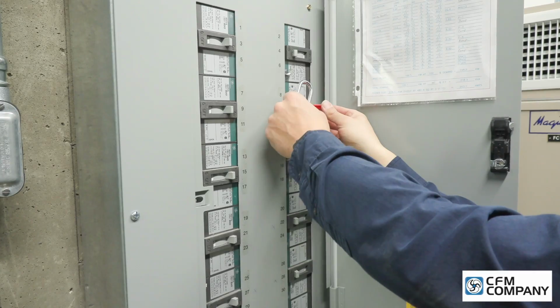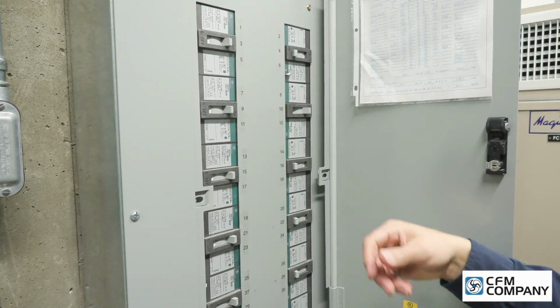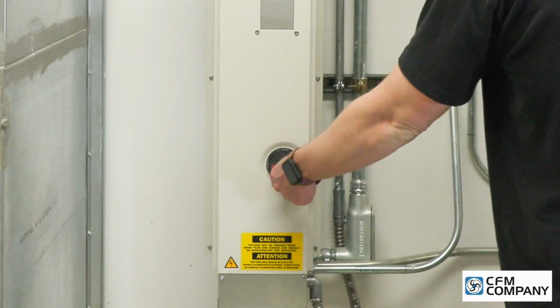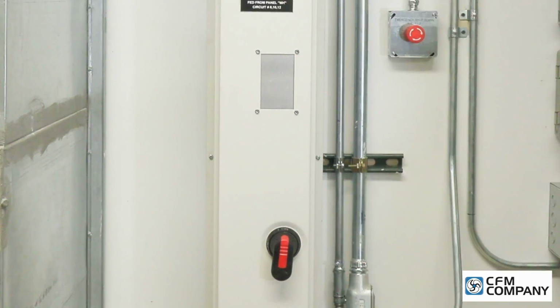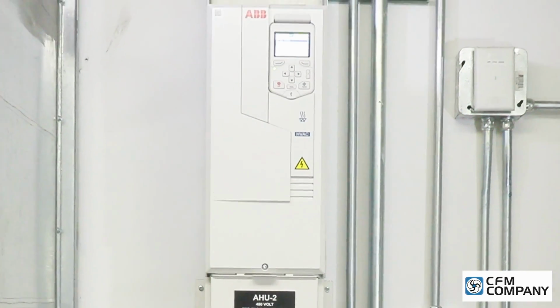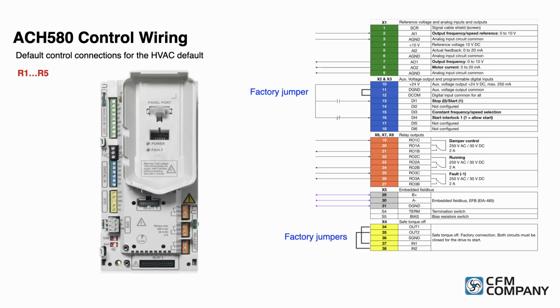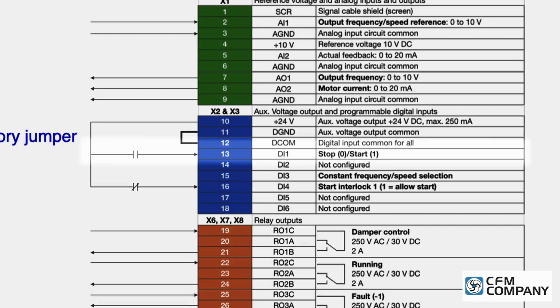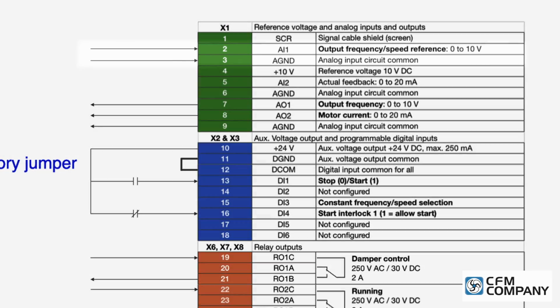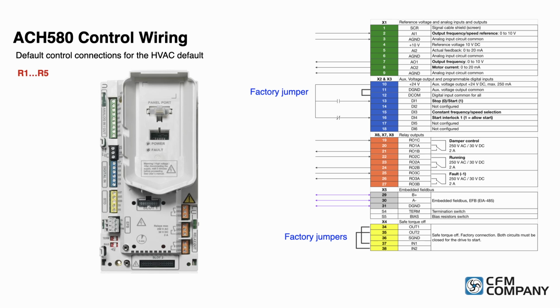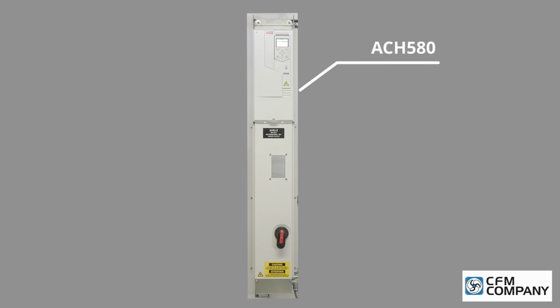Making certain that all personnel are out of the equipment and that they are at a safe distance away from the drive enclosure, remove the lockout tagout from the main circuit breaker and energize the equipment. Apply power to the drive enclosure and perform the standard startup programming for the new ACH580 drive. Once programming is complete, verify motor rotation. Verify that all field controls, including start-stop, start interlock, frequency reference, and status, are working properly with the building automation system. With the stay-in-place bypass replacement complete, the user can experience a long service life from the new ACH580 drive.